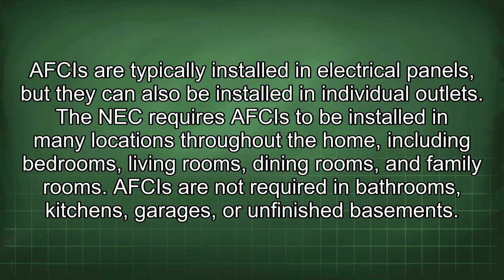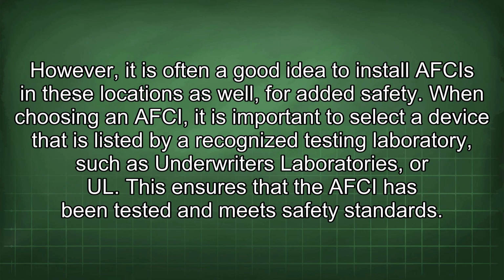The NEC requires AFCIs to be installed in many locations throughout the home, including bedrooms, living rooms, dining rooms, and family rooms. AFCIs are not required in bathrooms, kitchens, garages, or unfinished basements. However, it is often a good idea to install AFCIs in these locations as well for added safety.